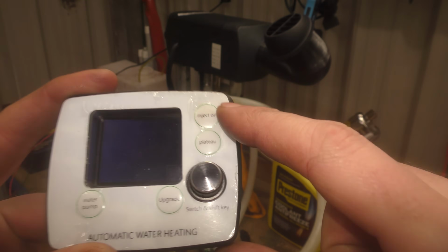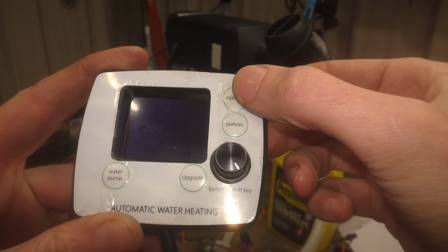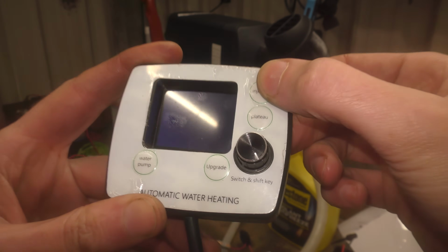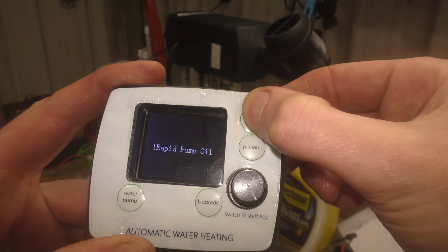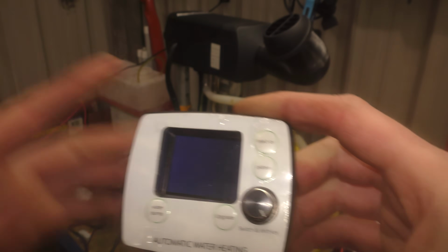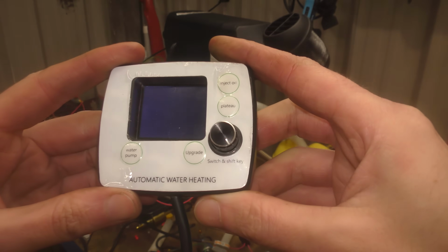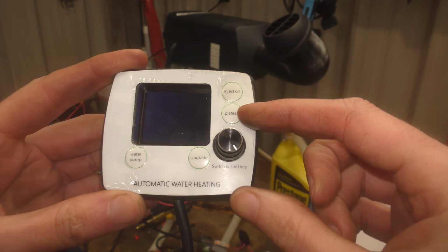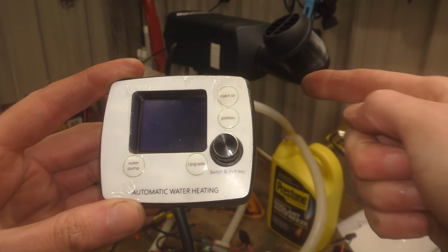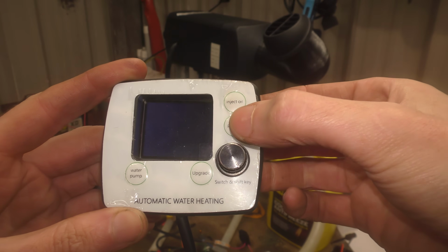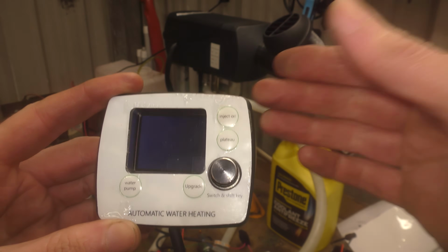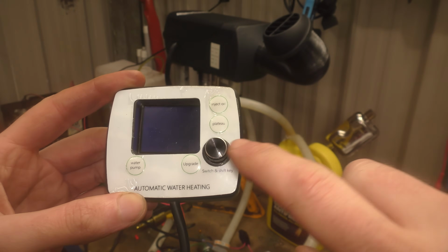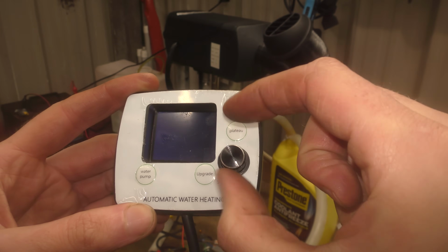So we'll start with this one. Inject oil: if you press and hold this while the heater is off, it runs off the fuel pump, so you can prime the system. Plateau mode: if you're above 1500 meters, you press and hold that to start the system, and it starts with a different fuel map for high altitude. Normally you just press and hold this rotary knob and button, and that starts it.